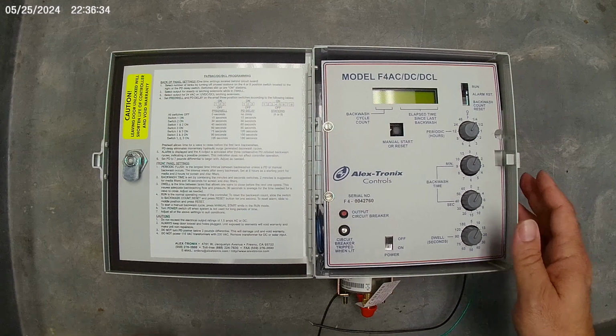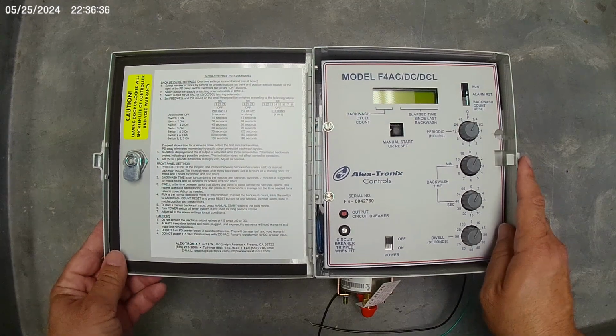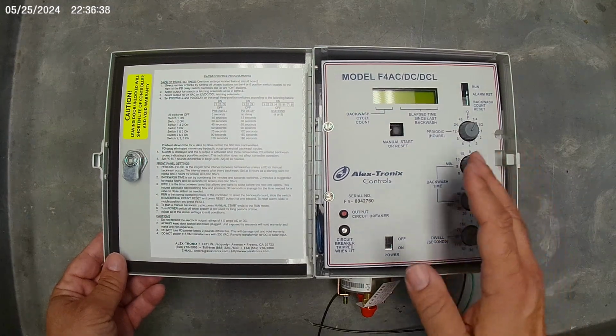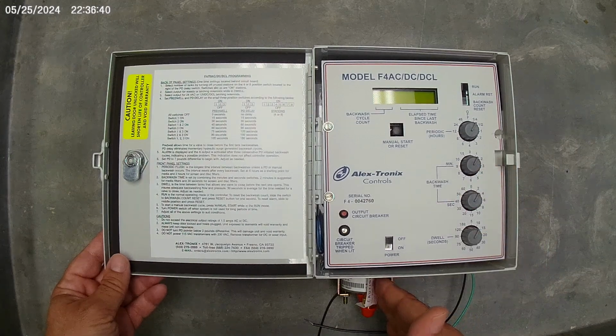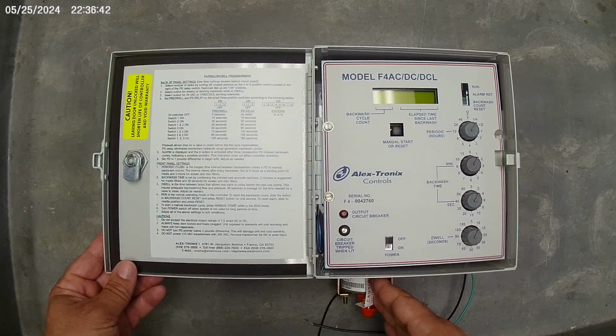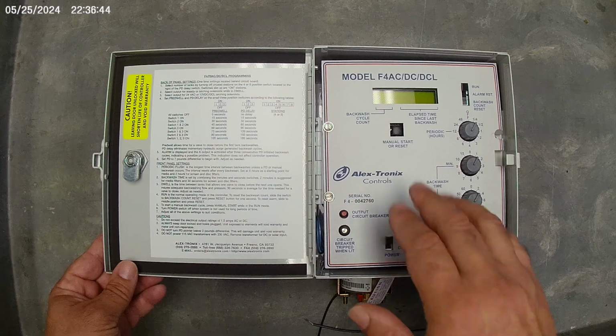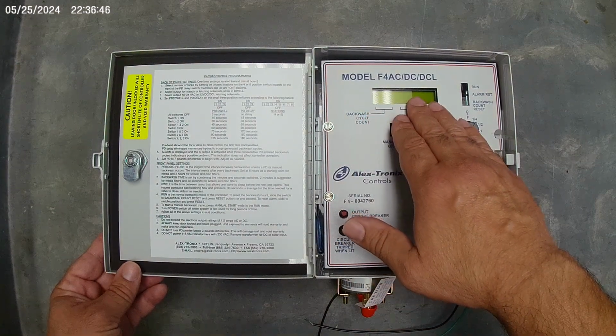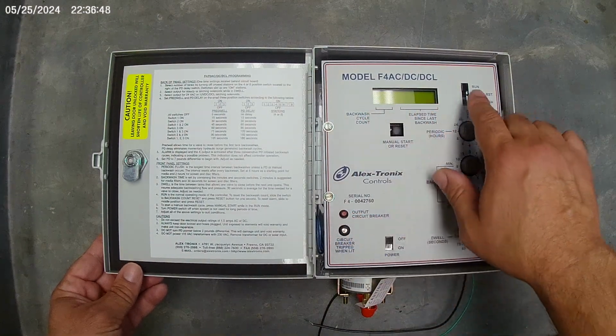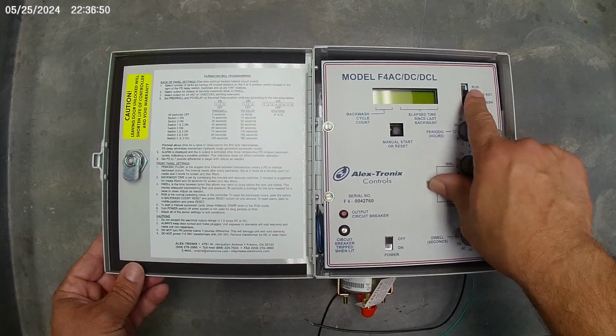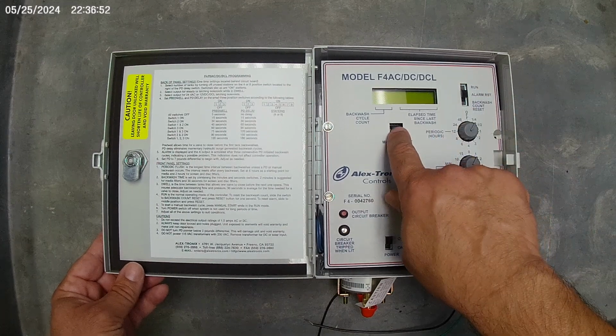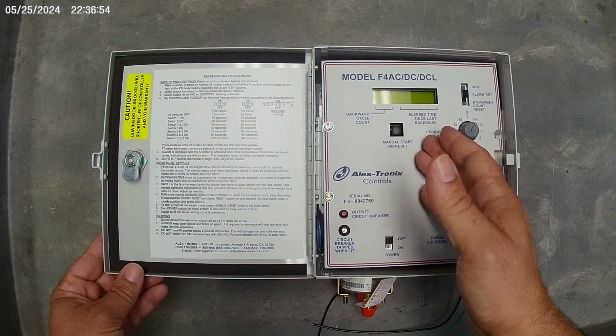As mentioned before, these controllers have an alarm mode. If the controller encounters 3 back flushes based off of pressure without going back to normal operation in between, it will go into alarm mode. It will say alarm. And to get it out of alarm mode, you move your function switch to the middle, alarm reset, and hold down the button. That will clear the alarm.